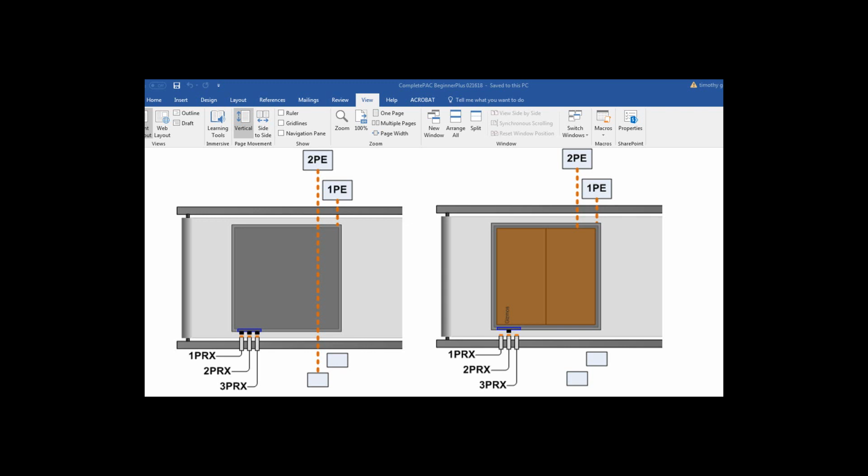Now in this case, since you're sensing the tray, an absence of any bolt heads or a value of 0 is plausible. Typically you wouldn't use that, because anything could block that photo eye, and if you're not sensing any bolt heads but you allowed for a 0, then if someone put their hand in front of it, it would read, of course, nothing and say that tray 0 is there. So each tray in my imaginary system has a pattern of bolt heads, anywhere from, we'll say, 1 to 3 total, and in different positions.